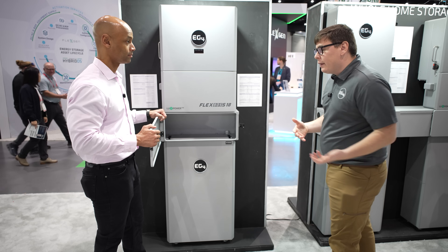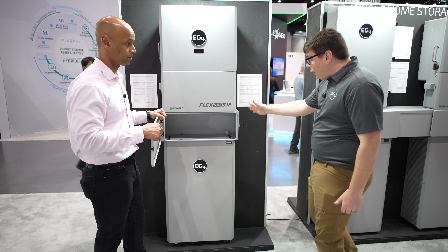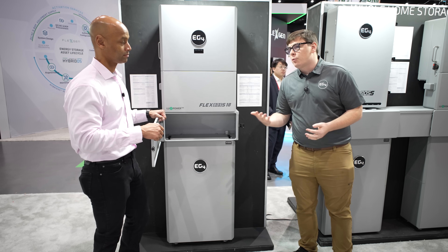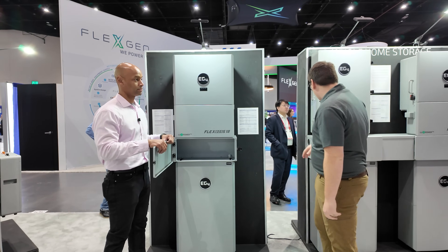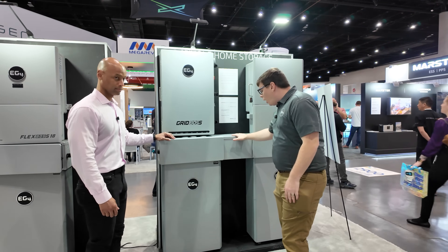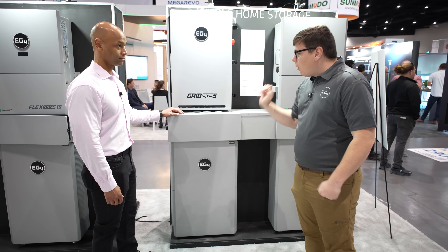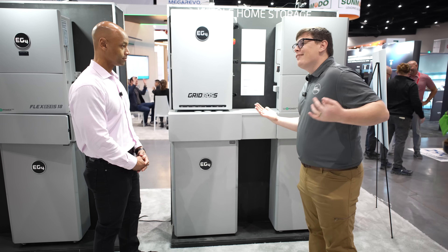What if we're going to connect multiple batteries? The standard single conduit box has a bolt pattern that allows you to use a 2-inch conduit to connect multiple single packs, and a lot of guys just do that. But for people wanting a more elegant solution for a standard 2-battery system, we've got a couple other solutions at this show. The 2-battery-wide solution looks really nice compared to two boxes with a pipe, and it's a single piece that's actually less than double the cost of the two individual boxes — as a cost shark, that's exciting to me.